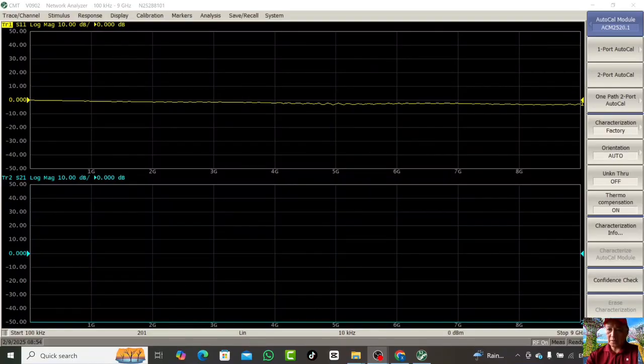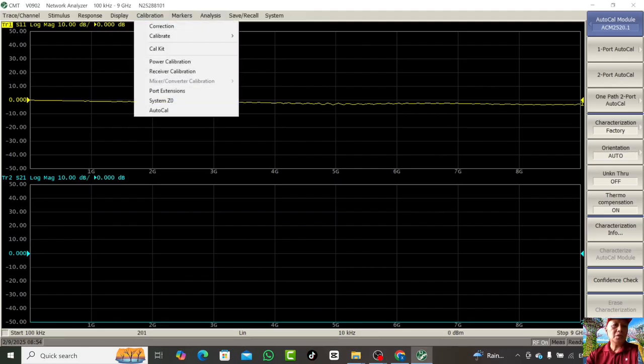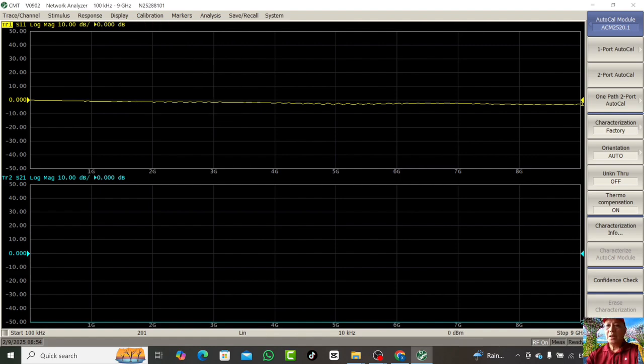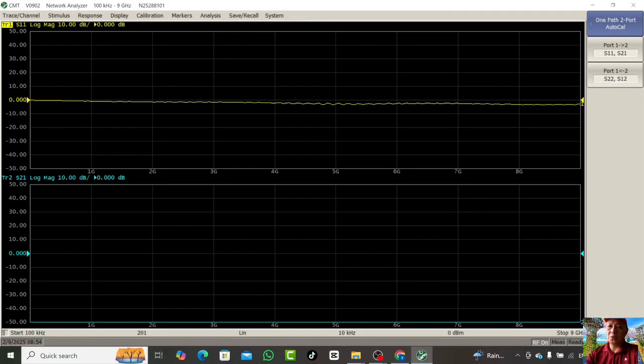Okay, let's start the calibration. The calibration kit is the ACM 2520 auto calibration module. So what I should do is choose calibration and then auto calibration, and because we are testing the filter's frequency response, we should choose One Path 2-Port AutoCal.